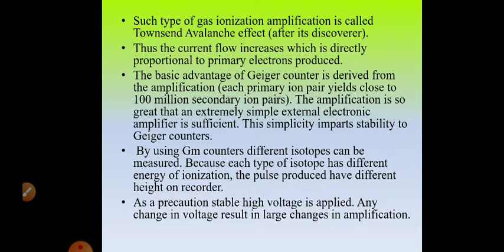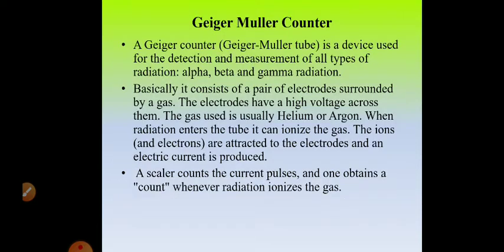As a precautionary measure, a stable high voltage is applied. Any change in voltage results in large changes in amplification. So a stable high voltage is required.